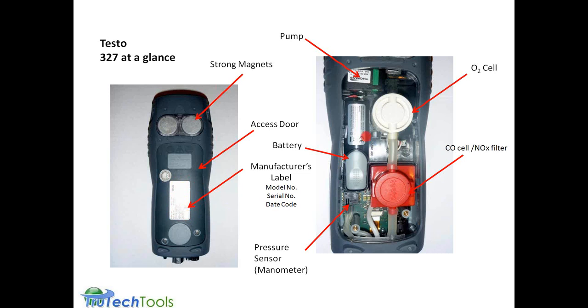the factory in Germany. The pump here, once you remove the battery door, there's two Phillips head screws and a little lip that falls under a groove inside the top part here. Once you remove that battery door, you'll see inside the pump, just user serviceable, but almost never needs to be serviced. It's a very rare service item. It's the way they've got it filtered and protected. The pump just keeps running for years. If we follow going down here on the left, we have the lithium ion battery, which is replaceable if necessary. Haven't heard of too many battery replacements in the course of 4 or 5 years. You may need one maybe in 5 or 6 years.